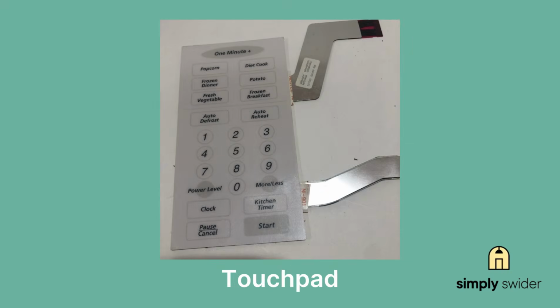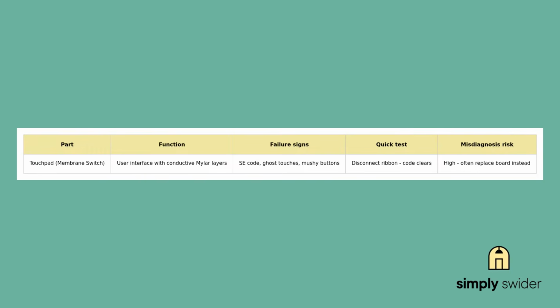The membrane touchpad runs anywhere from 35 to 135 bucks depending on your model. This is the part you'll replace most often. Fair warning though, some of these are heat fused to the plastic door frame and don't peel off easily. If it's glued down solid, that might be where you call a pro. The silver conductive coating on these things is thin, so don't remove and reinstall multiple times or you'll wear it right off.